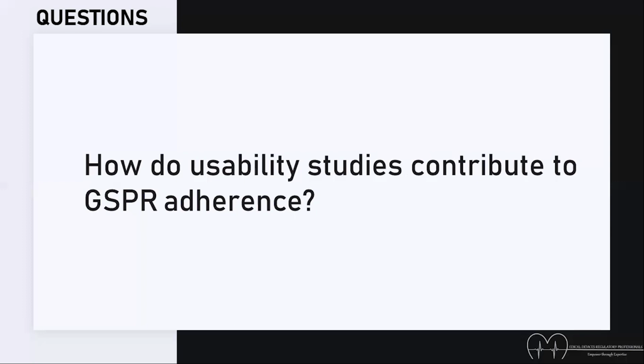So you have to be a little bit careful to analyze and see where this joins in. And in the past, we have seen some manufacturers basically abuse usability studies by calling them clinical studies. And that, of course, is no longer applicable. We see more and more usability studies, usability engineering, not only as part of active devices, as it was initially when the standards came in place, but now also for non-active devices. More and more expectations, but you have to find where they are.